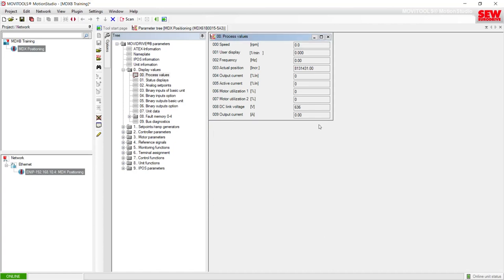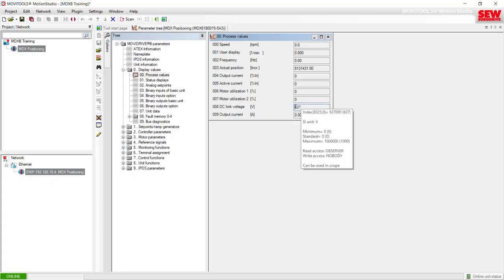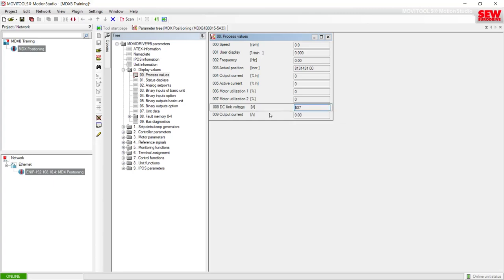If you're looking in the lab instructions, one of the first questions you may see is: what is the current DC link voltage of the motor drive? We can see that right here in parameter 8 — the DC link voltage is currently at 637 volts DC.